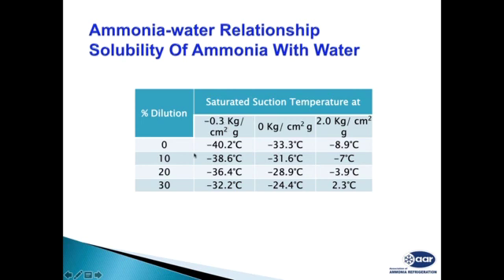See, this is -40. If you have 30% water in the ammonia, the ammonia pressure will rise, so instead of -40 you will get -32. It does not freeze the water because it has become one solution. Oil does not mix with water, and oil does not mix with ammonia, but water and ammonia mix together and become a hydrous solution. So it does not freeze. But of course, the presence of water in the ammonia affects the functioning of the valves and controls because it starts corrosion of the material.